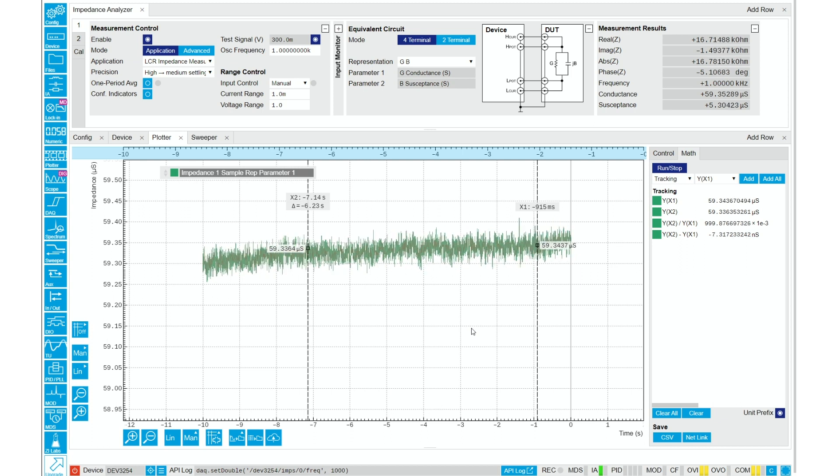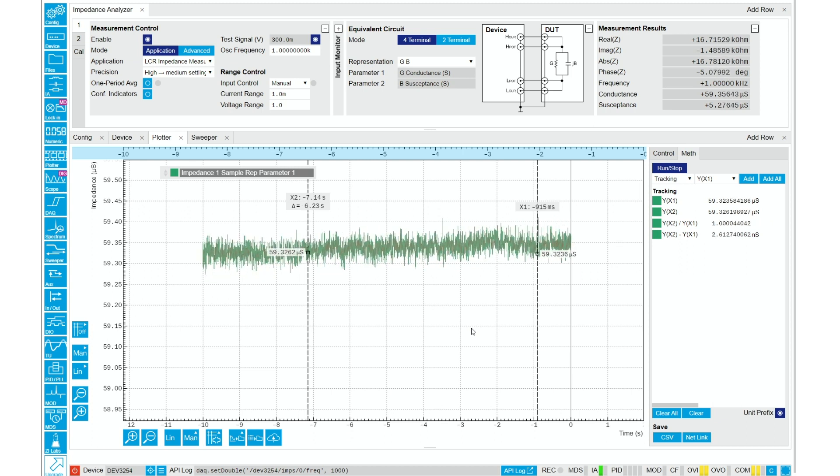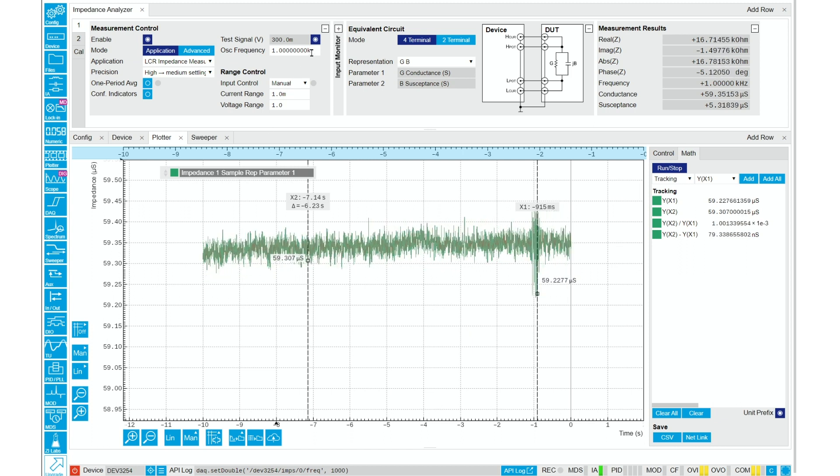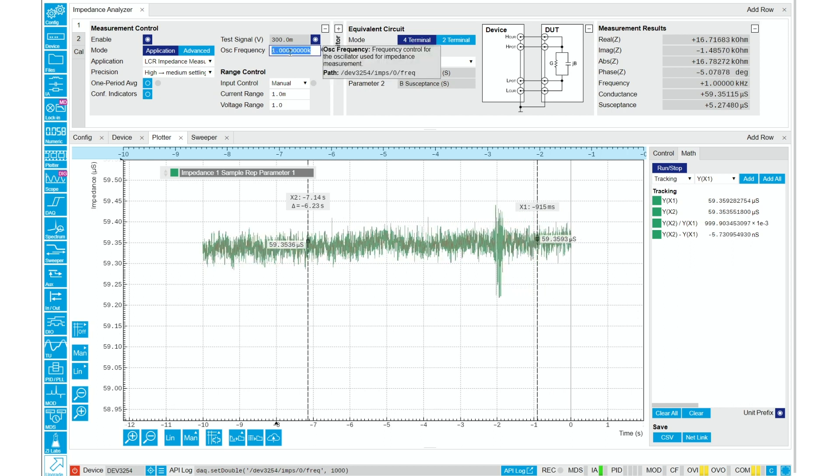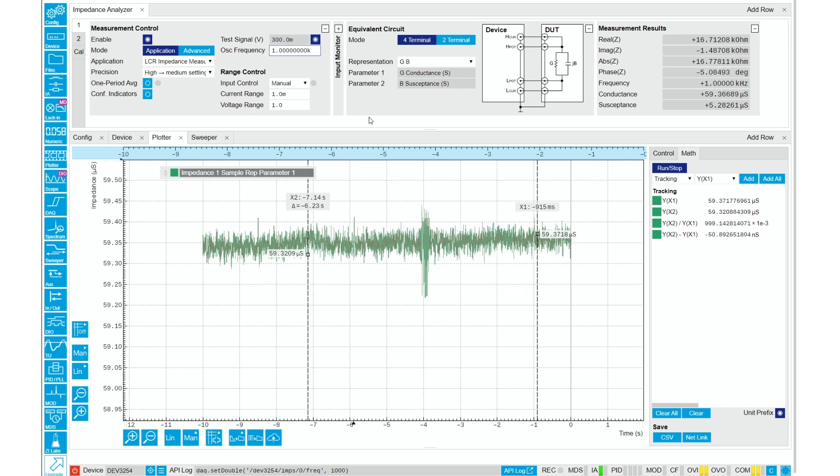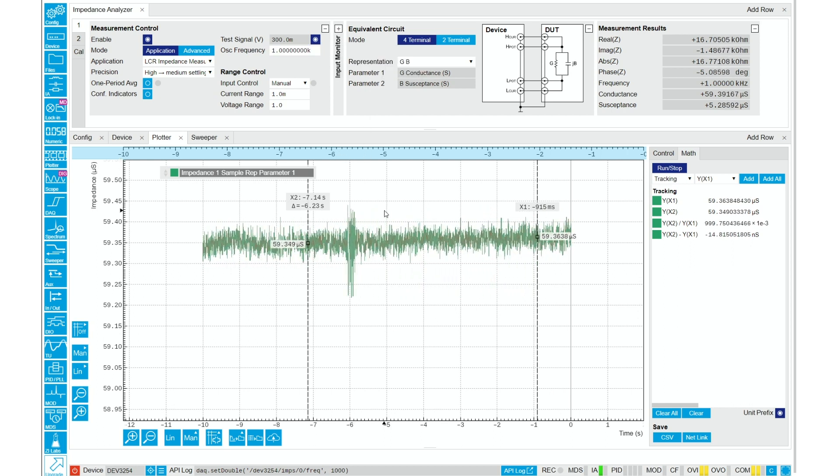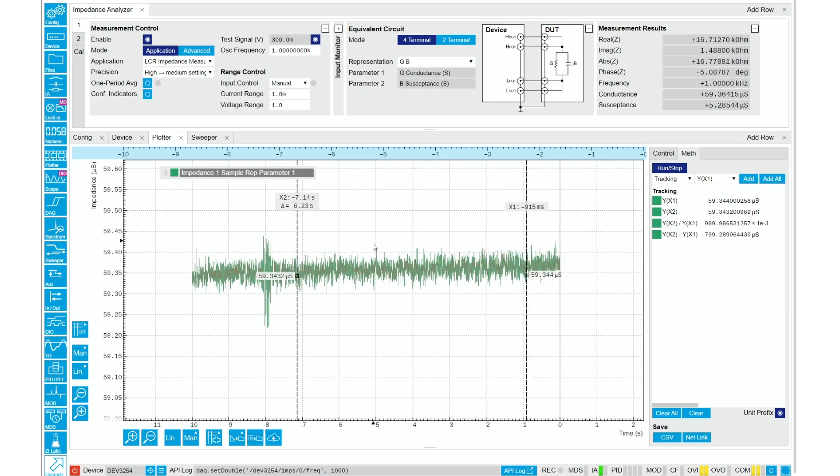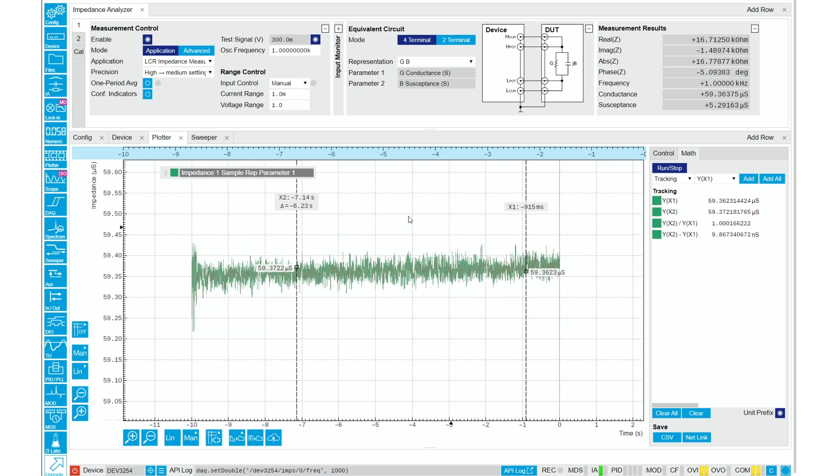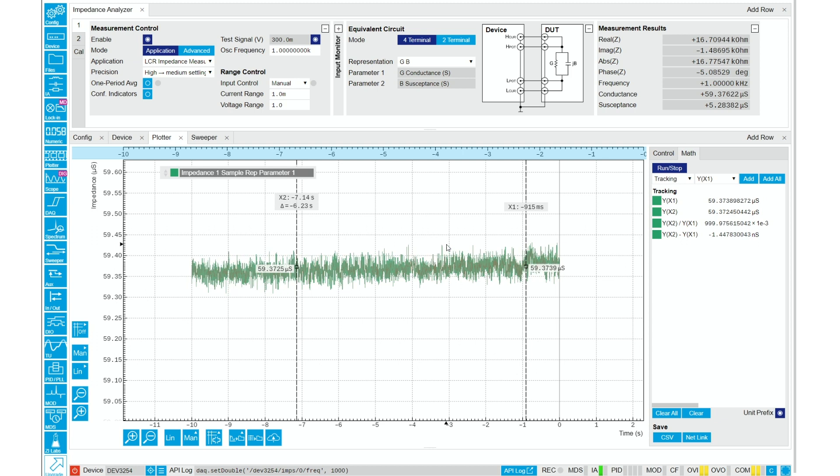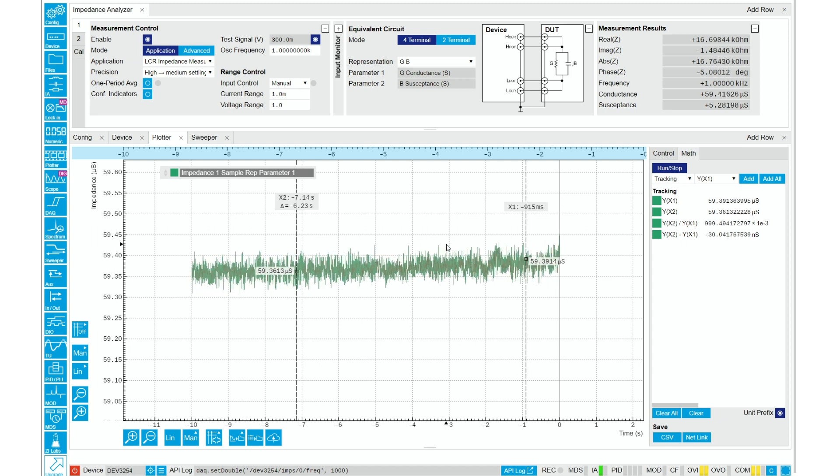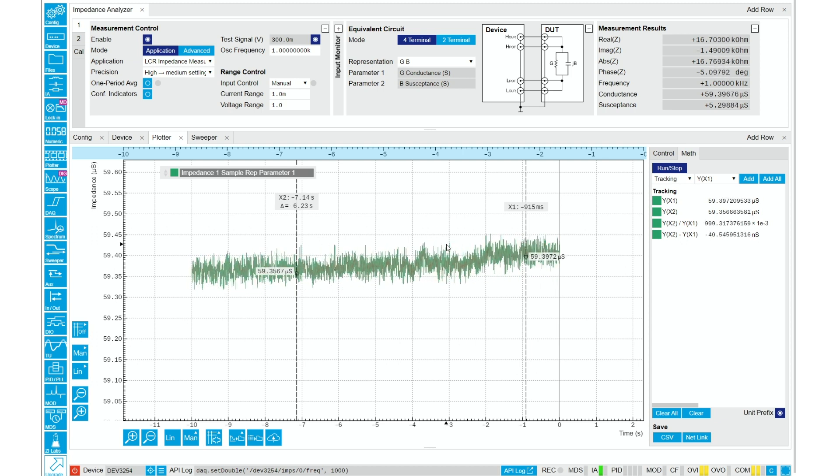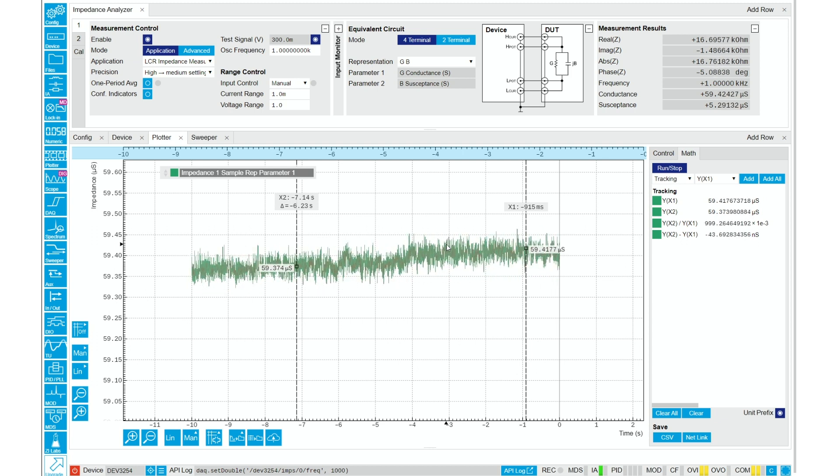Typical probes have a characteristic frequency at 1 kilohertz. If we set the MFIA frequency here, we can measure the impedance of this conductive liquid and monitor how it changes over time. Dividing the measured conductance by the cell constant gives us the conductivity in units of Siemens per centimeter.